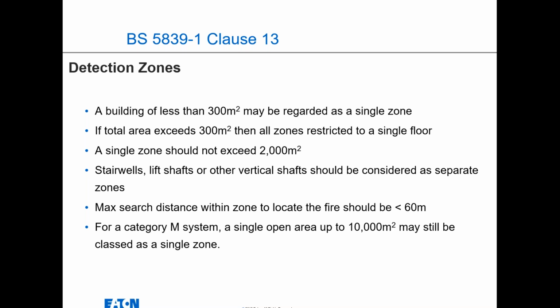So if a fire brigade entered the zone, because it's a conventional panel, from that point of entry to the zone, they shouldn't have to travel more than 60 meters. And that's not as the crow flies, that is practically 60 meters. They shouldn't have more than that, so you should be looking at that in your designs. And for a category M system, a single open area is a maximum of 10,000 square meters. Again, M systems are very, very few and far between, because most insurers want to protect the asset.